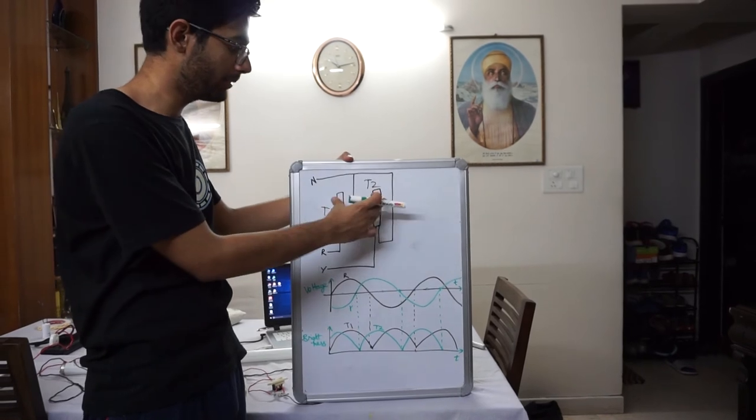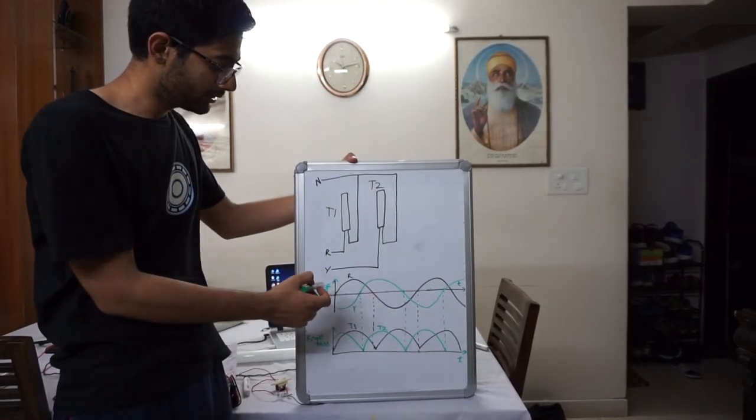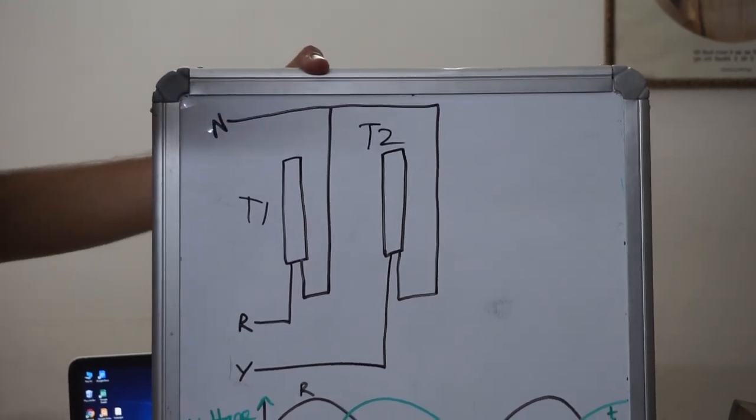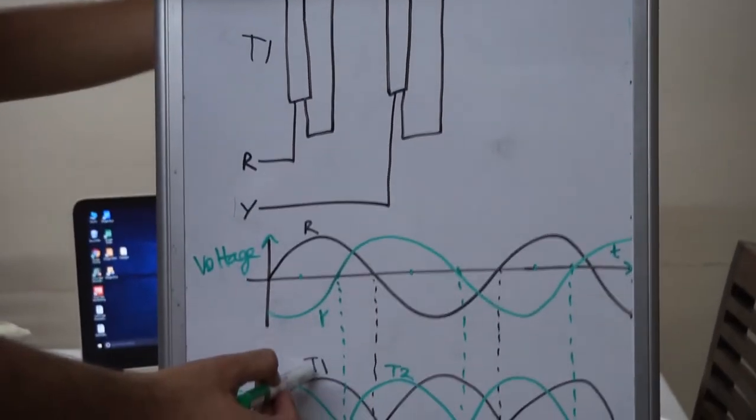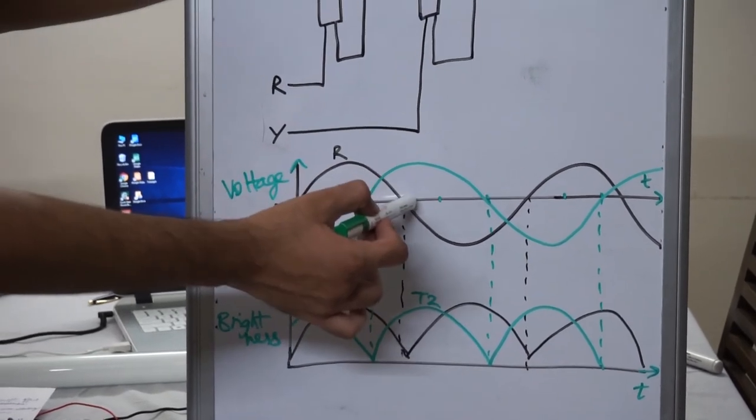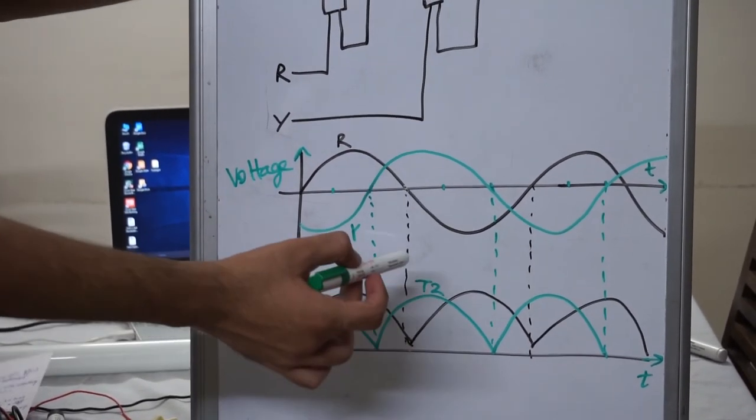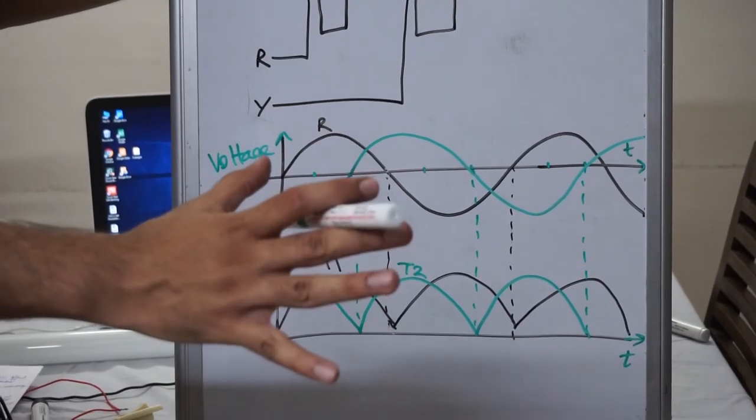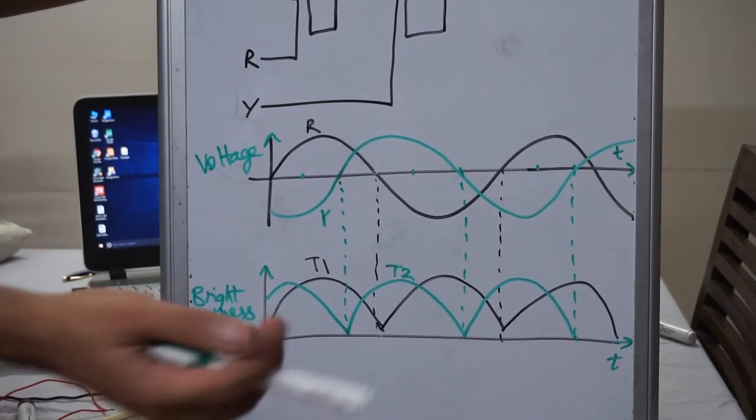Connecting adjacent tube lights to different phases so that the net brightness is not zero at any point of time. Even when the brightness due to T1 is zero when the R phase voltage is zero, the brightness of T2 is not zero, so the net brightness will not be zero and the stroboscopic effect will be greatly reduced.